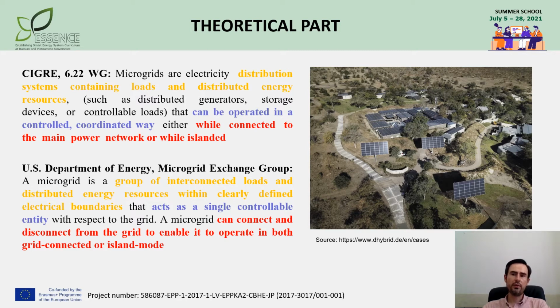Since that time, the definition of microgrid includes three major requirements. The microgrid boundaries shall be clearly defined. Usually, there is one point of coupling with the main grid. The resources within the microgrid shall be controlled in a coordinated way to meet the internal goals of the microgrid. The microgrid shall be able to operate in parallel with and independently from the main grid.